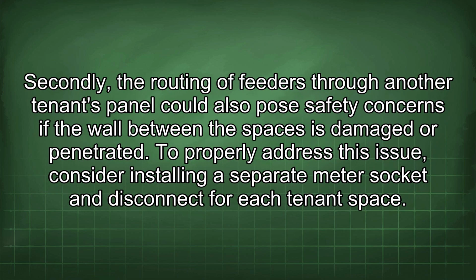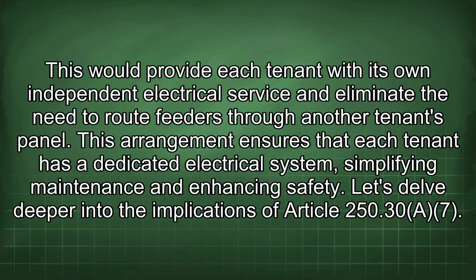Secondly, the routing of feeders through another tenant's panel could also pose safety concerns if the wall between the spaces is damaged or penetrated. To properly address this issue, consider installing a separate meter socket and disconnect for each tenant space. This would provide each tenant with its own independent electrical service and eliminate the need to route feeders through another tenant's panel. This arrangement ensures that each tenant has a dedicated electrical system, simplifying maintenance and enhancing safety.